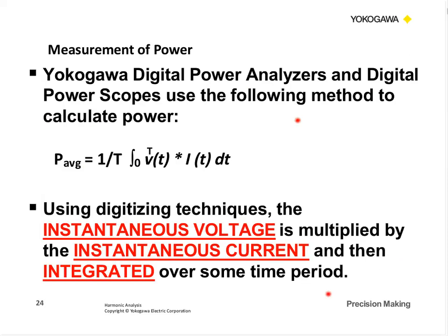So with the measurement of power, showing the formula, what we do is take the instantaneous voltage times that instantaneous current. These are the digitized values. Their voltage and current are sampled simultaneously, so we take all those instantaneous values of voltage times the instantaneous value of current, accumulate those in a working memory, and integrate those over some time period, 0 to t, and then multiply by 1 over t. So it's the digitized value of voltage times the instantaneous digitized value of current, and then integrated over some time period. And this time period can be a variable. It's a front panel variable, usually on the front of our instruments.